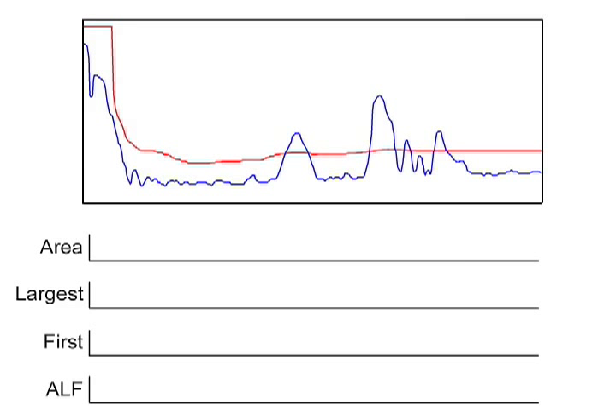To give you an idea of how this works, let's look at this example. First, we will look at the area component. Each of the echoes that cross the TVT define a specific area. The echo with the largest area is given the highest score. In our example, this is the second echo.